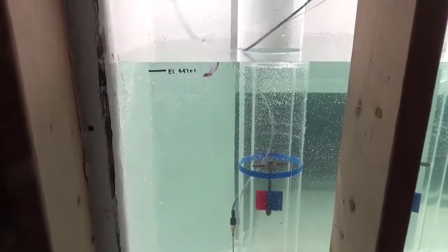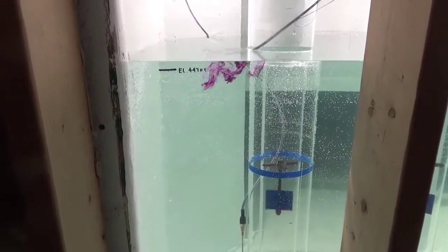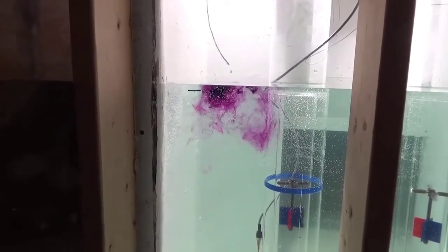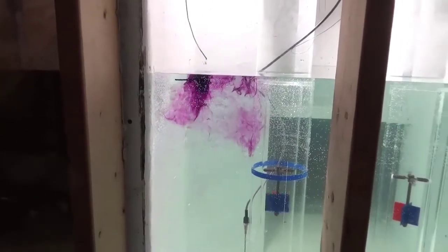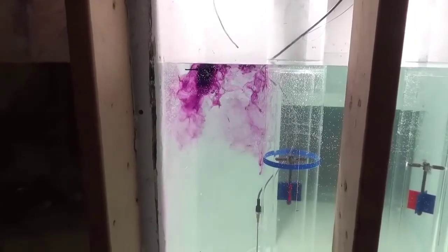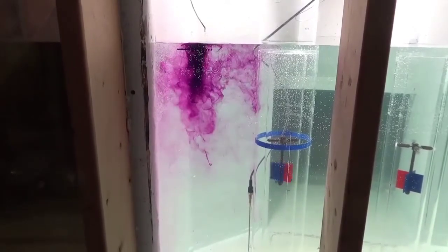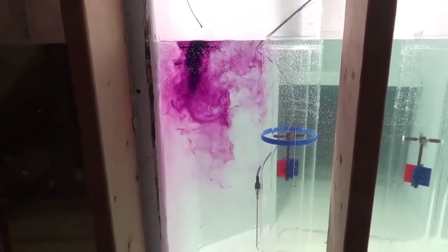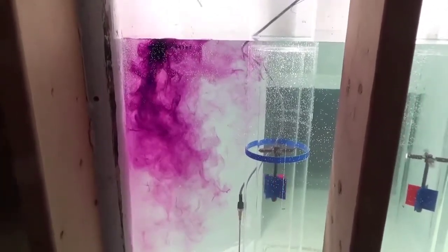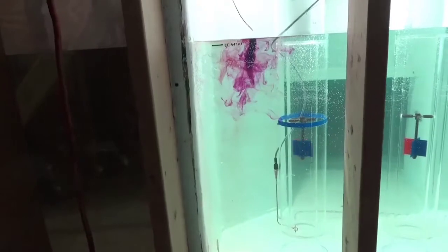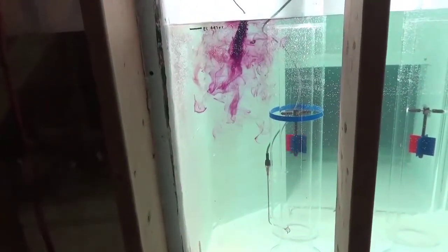We'll go ahead and see. Sometimes we may need to let this go a little bit longer, but we'll see if we can get one to organize. Sometimes they'll come quite quickly and they'll be intermittent. They are organizing into type 3s, but they're not frequent. You can see a little bit of swirl trying to form. And this is low water level. We're going to let this organize a little bit. Okay, I think we're going to get one to organize here, it looks like.